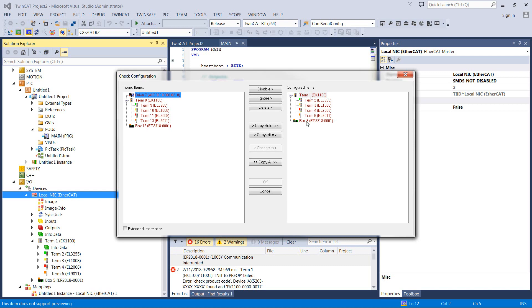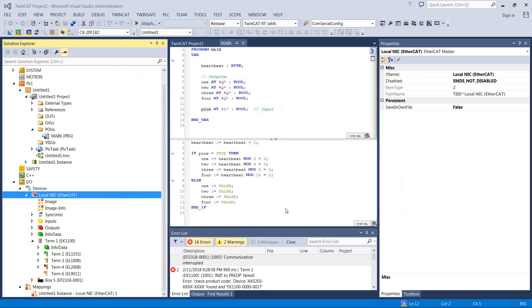Okay, so it says, hey, I found this drive and it's ahead of all of this other stuff that used to be here. This is what I know about. This is what I've just found. So you can come over here, click, you know, I want this guy, I want him to be here, and I want him to be right before him. So it all goes green. That means, hey, what I saw is now what I have configured. Hit OK.